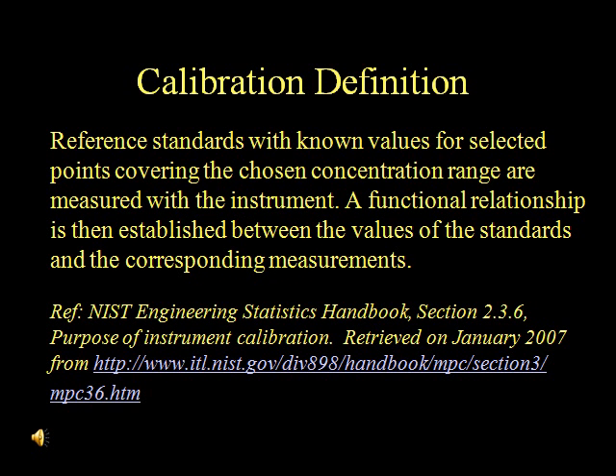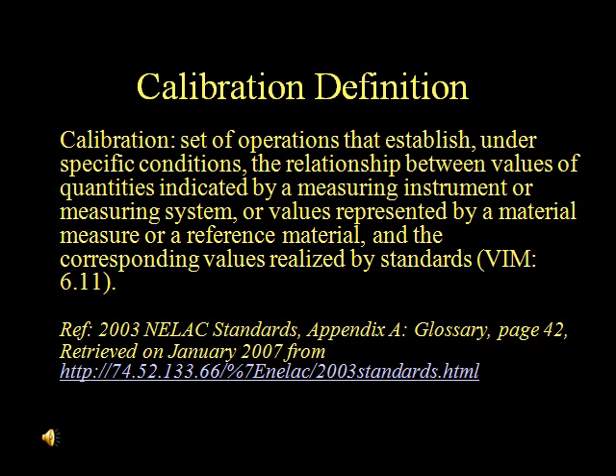We define the term calibration as reference standards with known values for selected points covering the chosen concentration range that are measured with the instrument. A functional relationship is then established between the values of the standards and the corresponding measurements. The 2003 NELAC standards definition of calibration also provides us with the concept that a relationship is indicated by the values of the represented standards and the corresponding values realized by the standards.